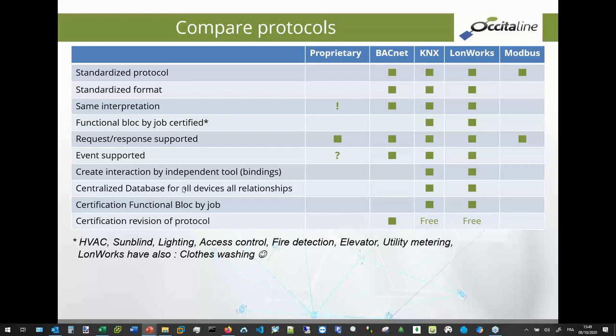Is it possible to create interaction with independent tools? It's impossible in BACnet. With proprietary, an independent tool is impossible because it's proprietary software for that. In Modbus, you can't create any connection between two devices. With this line, we will see that the only two protocols that are very open, very standardized, and interoperable are KNX and LON.